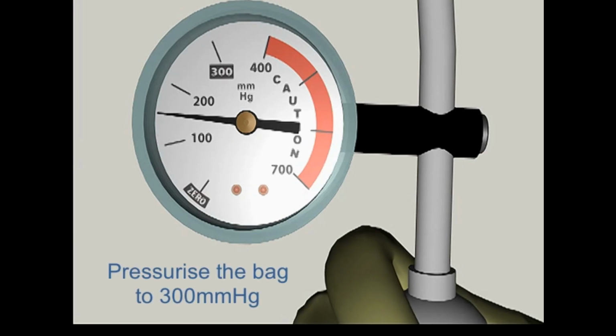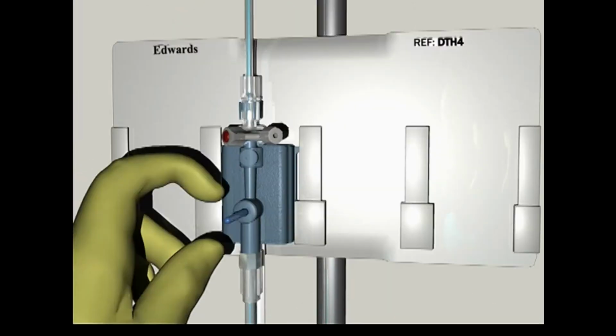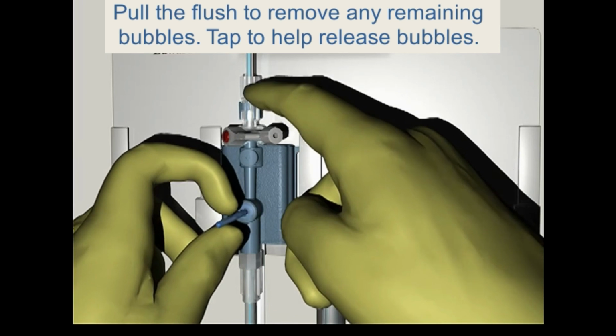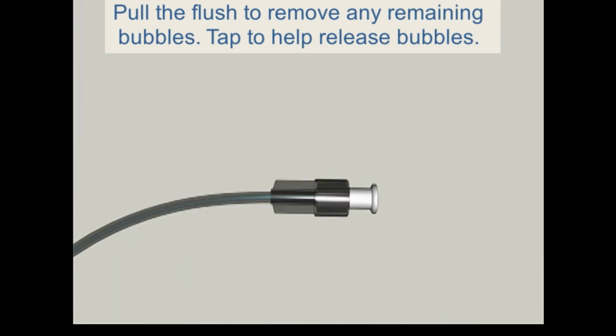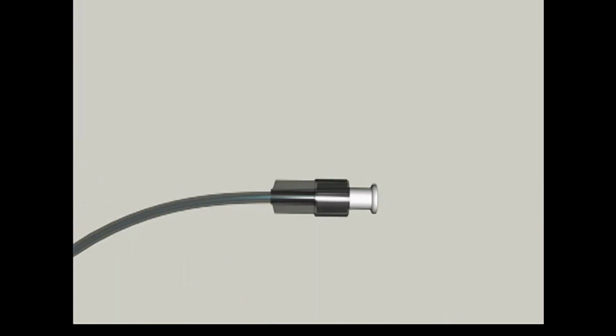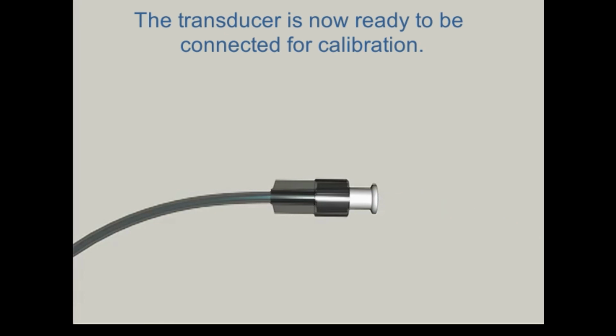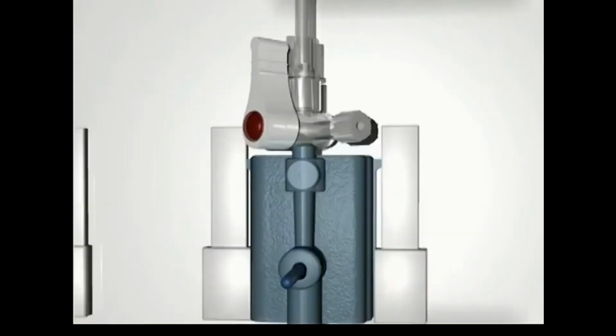Pressurize the IV flush solution bag to 300 millimeters of mercury. Pull the snap tab to flush the system under pressure while tapping on the tubing and stopcocks to remove any residual bubbles. After removal of any residual bubbles, connect the TrueWave transducer to the bedside physiologic monitor for calibration.